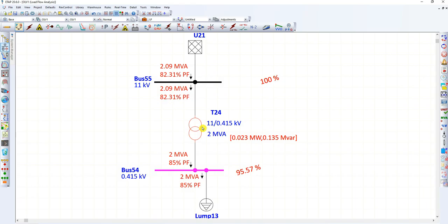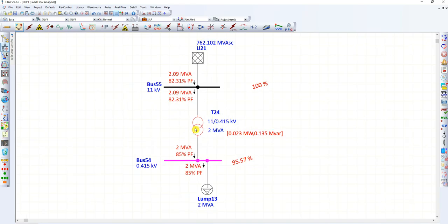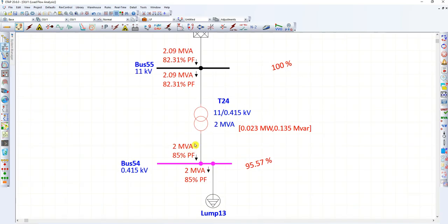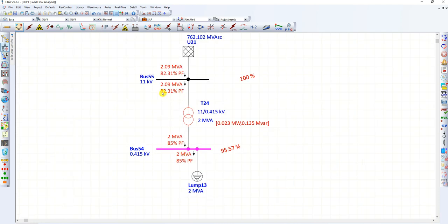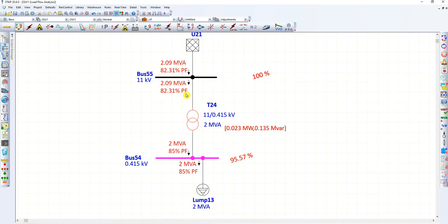That is the difference between an IEC transformer and an ANSI transformer. In the case of an IEC transformer, when the rating is 2 MVA, the input side must supply more than 2 MVA because it needs to compensate for the internal real and reactive power losses to deliver 2 MVA at the output. So the 2 MVA IEC rating is not the output terminal rating — it should be considered from the primary side, which includes transformer losses. The power factor here is 82.31 percent.